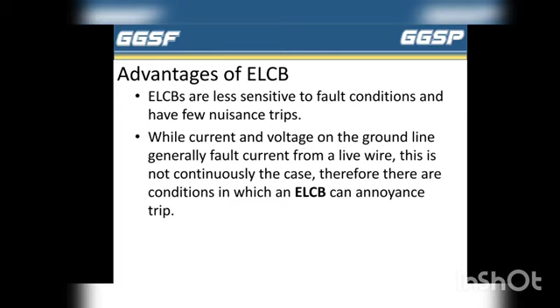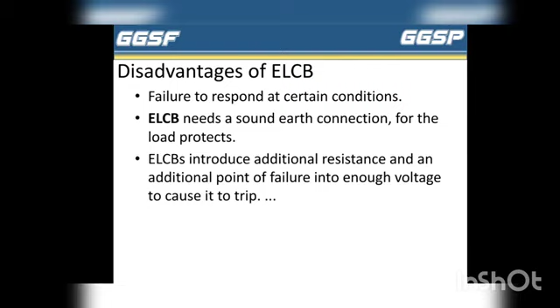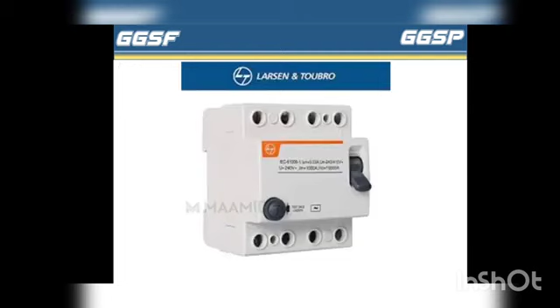Next is disadvantages of ELCB. First is failure to respond in certain conditions. Second, ELCB needs a sound earth connection for the load protection. Next, ELCBs introduce additional resistance and an additional point of failure into the circuit. This is the ELCB.